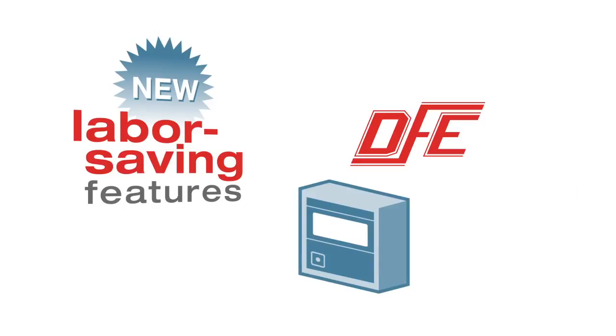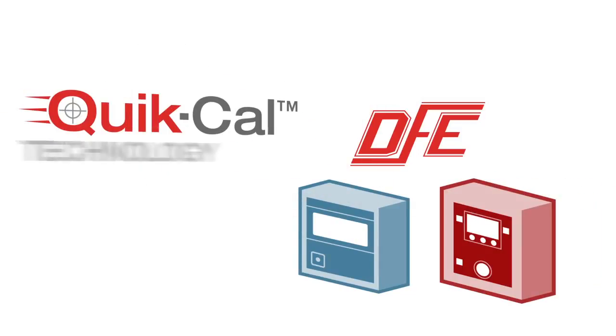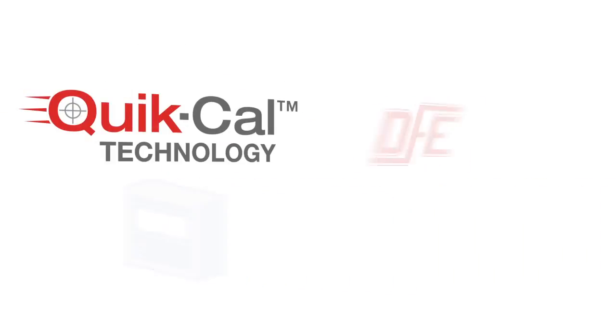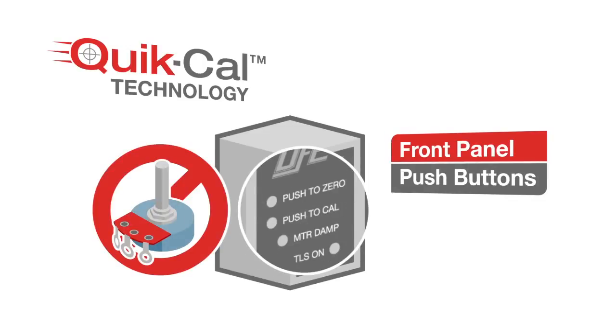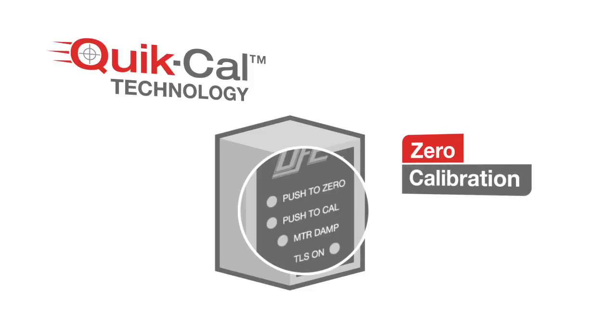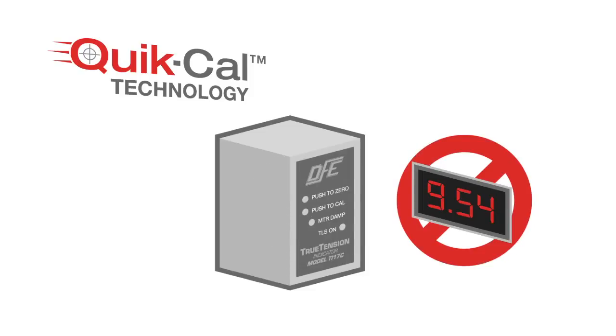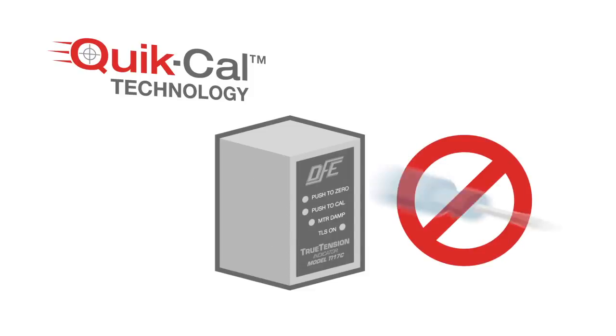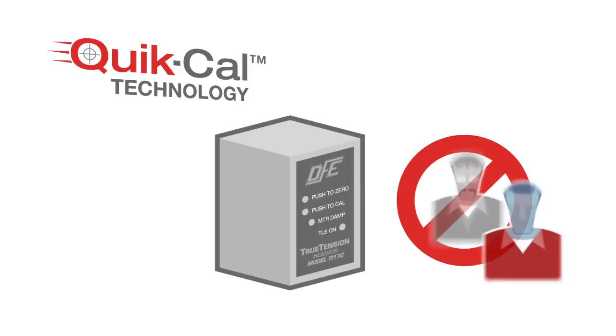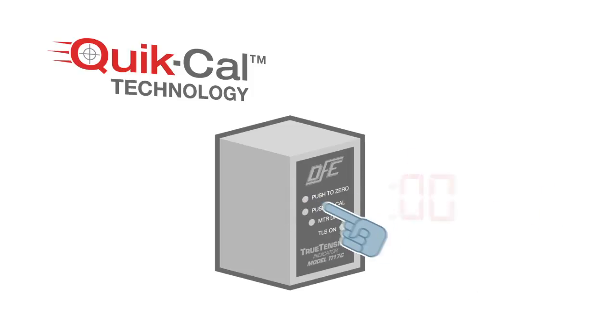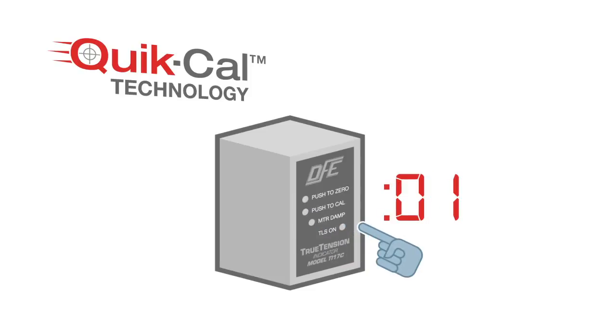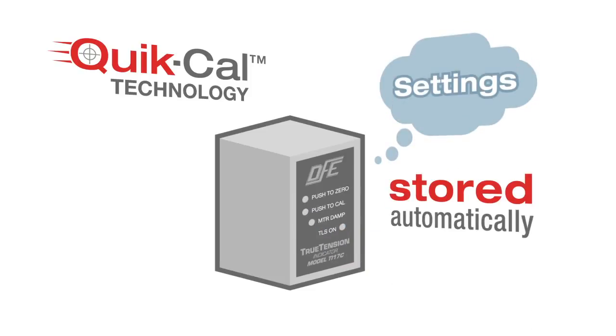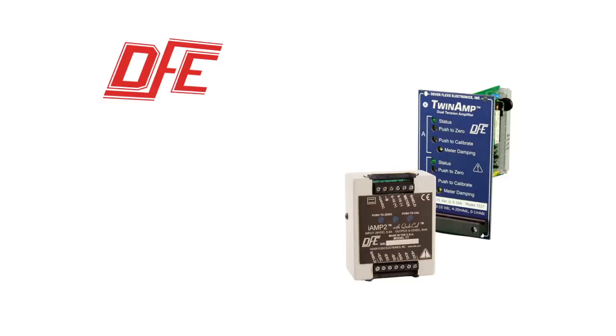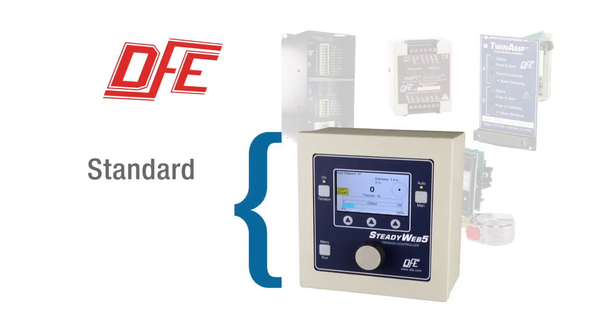One of the new labor-saving features of DFE's tension indicator and controller products is QuickCal technology. With QuickCal, the indication and control electronics use front panel push buttons instead of potentiometers for zero and calibration settings. No tension display is needed, no screwdriver is needed, no second person is needed. Each button is pressed once during the calibration procedure for 1 second, and the settings are stored automatically. Most of DFE's newer amplifiers, indicators, and tension controllers come standard with QuickCal.